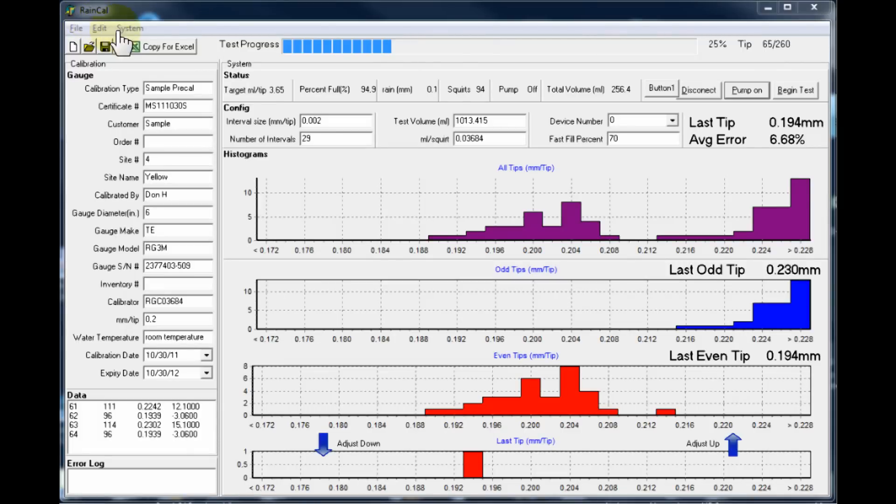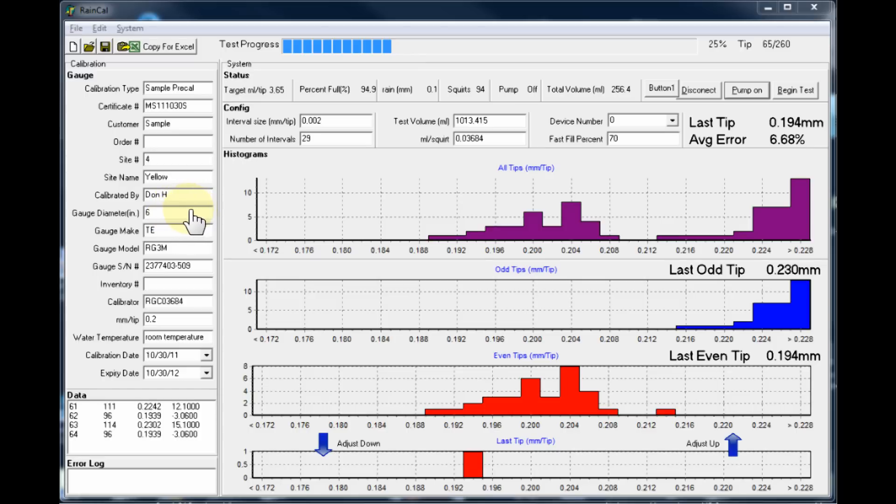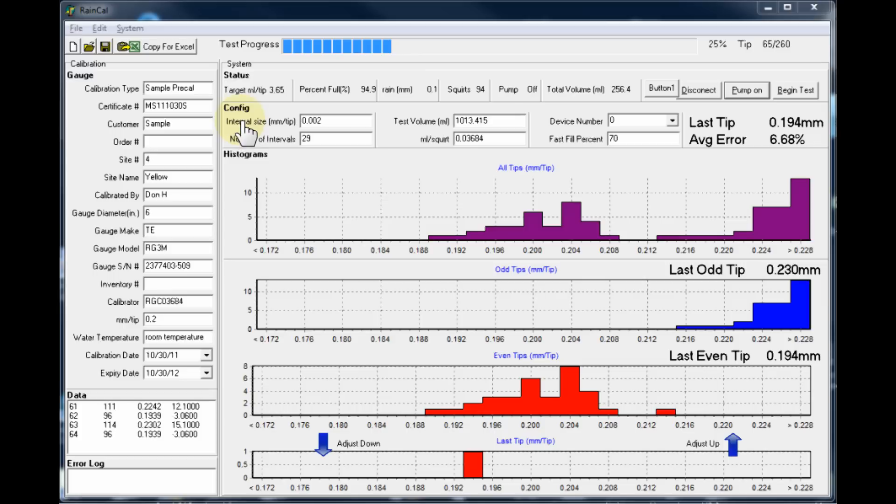This is the software that Lakewood developed for its digital rain gauge calibrator. On the left here, we can see various parameters of the gauge that are put into the software and are later fed through to the calibration certificate. Specifically, we can see the gauge diameter here and how many millimeters per tip the gauge is expected to produce. The software then takes a look at that and determines how many millimeters per tip is required.